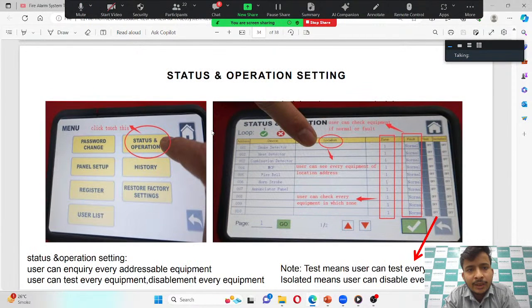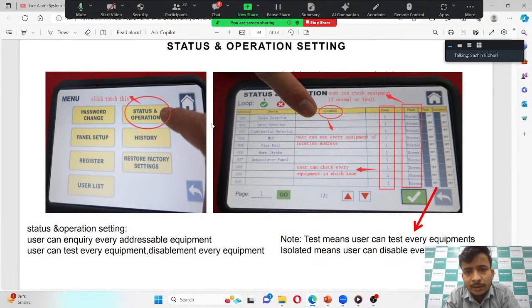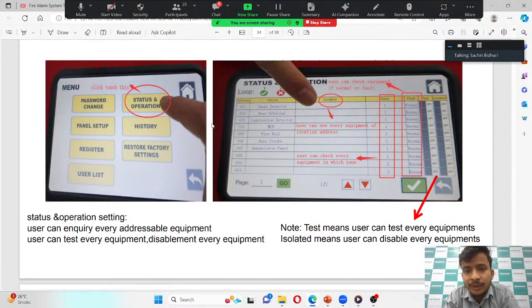In status and operation settings, you can monitor the devices connected with the panel. You can test those devices. If you press the test button, you can test that device. If you press isolate on or off, you can disable that device from the loop. You can monitor whether this particular device is working normally or if there is any fault. So you can monitor that in this status and operation.